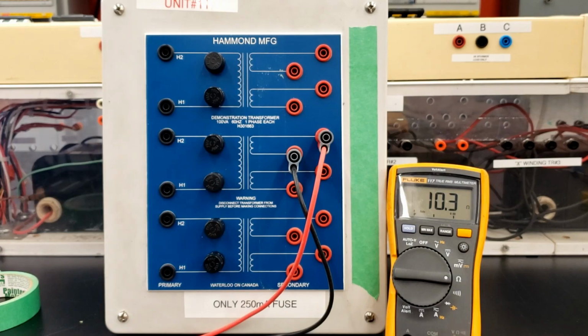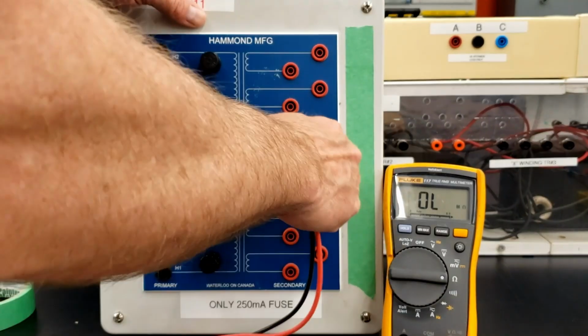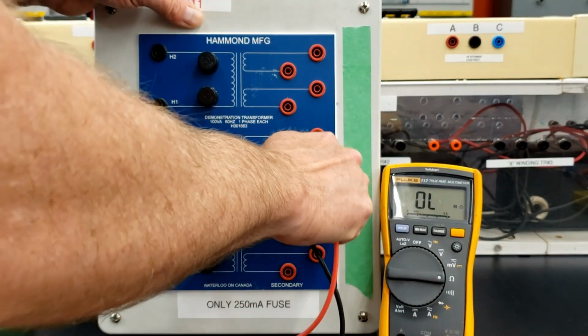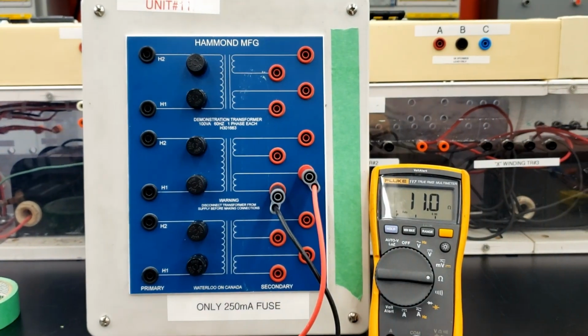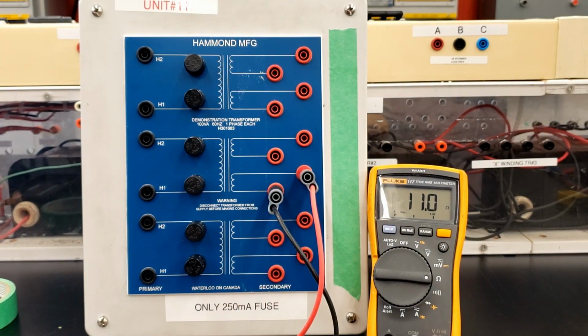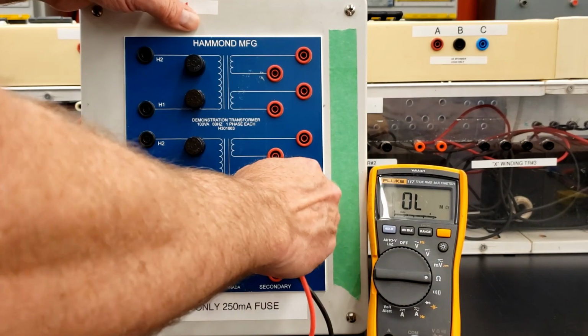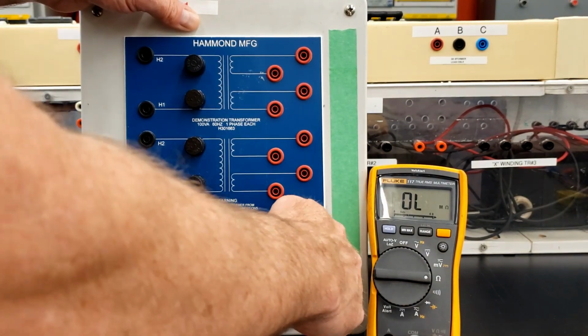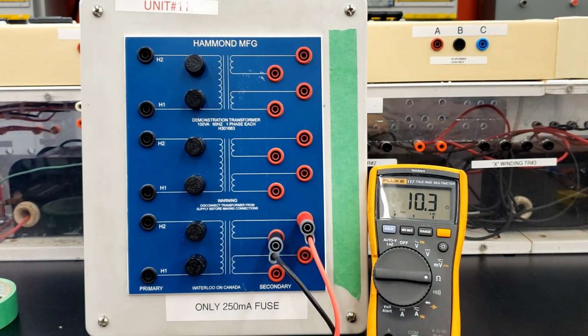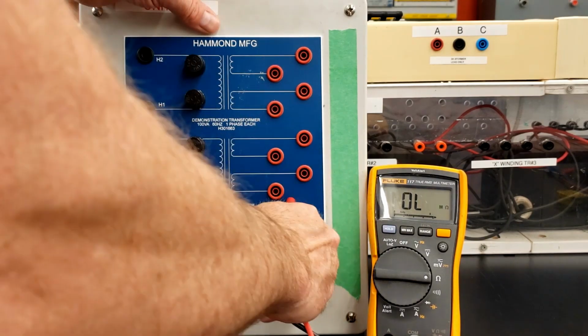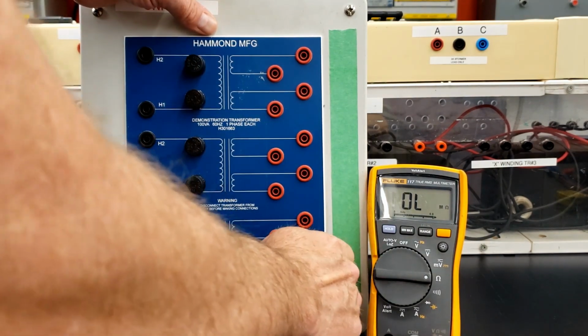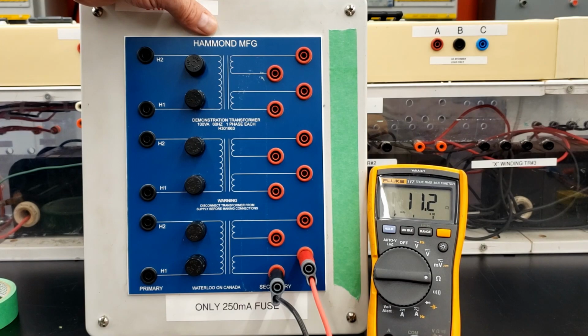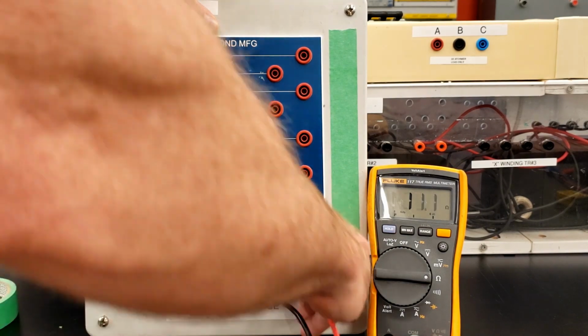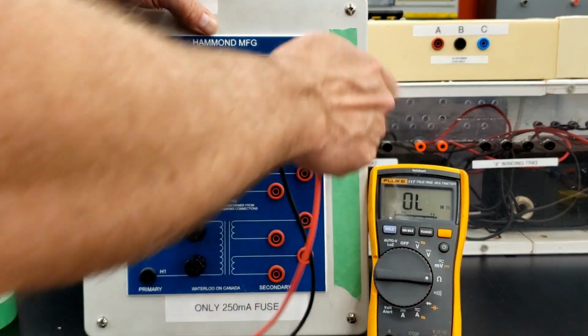There's 10 ohms there. Let's check the resistance on the second winding - 11 ohms. So 10 ohms seems to be the norm. Third transformer, first winding is 10, and the final one is 11. Looks good. So the only anomaly is this winding on the secondary.